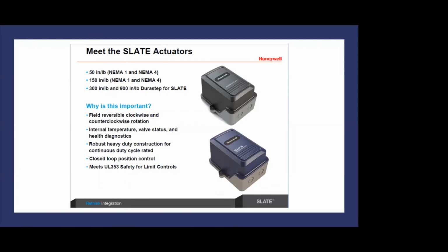Heavy duty construction, continuous duty cycle rated, closed loop position control. So it's just to the module and to the actuator and back. And we meet all the safety and limit controls of UL 353 with these actuators as well. And I've got to inject another building automation moment here. These are Modbus actuators. They're not hardwired actuators, and we're getting all sorts of temperatures, statuses, diagnostics, as Jeff just mentioned.